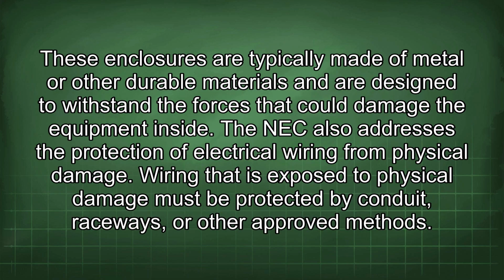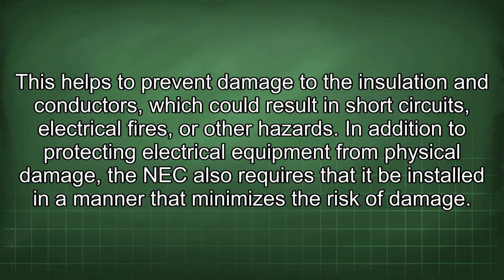These enclosures are typically made of metal or other durable materials and are designed to withstand the forces that could damage the equipment inside. The NEC also addresses the protection of electrical wiring from physical damage. Wiring that is exposed to physical damage must be protected by conduit, raceways, or other approved methods. This helps to prevent damage to the insulation and conductors, which could result in short circuits, electrical fires, or other hazards.